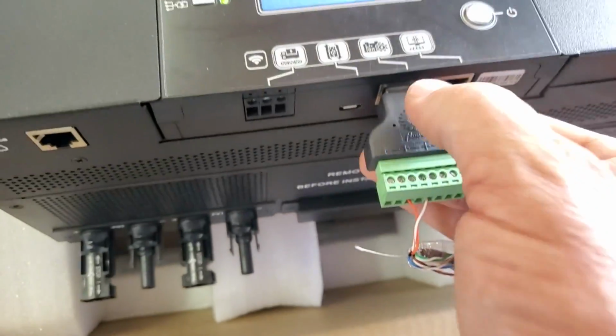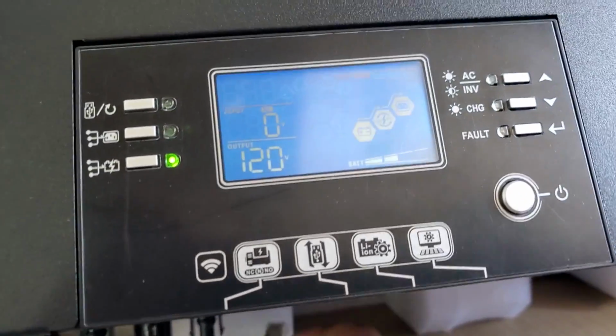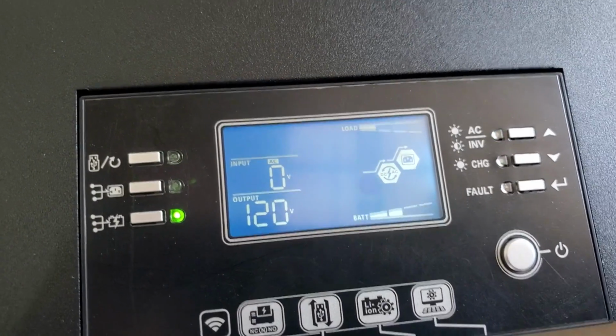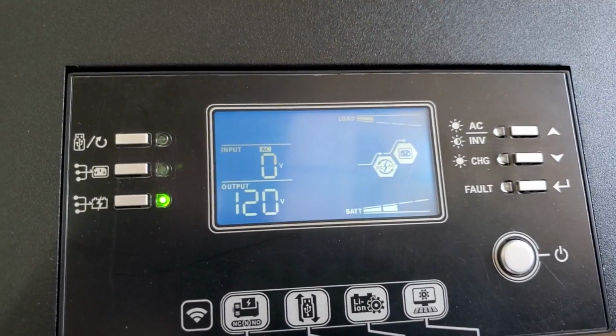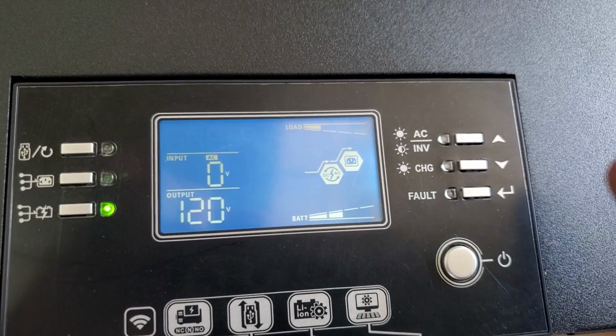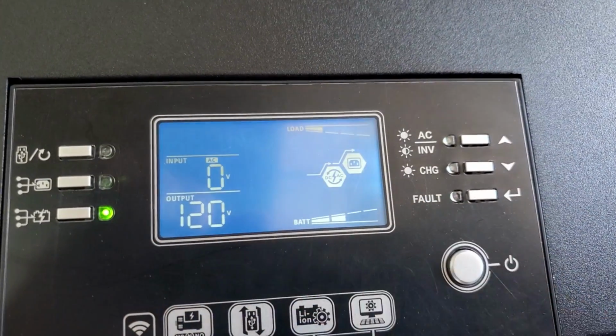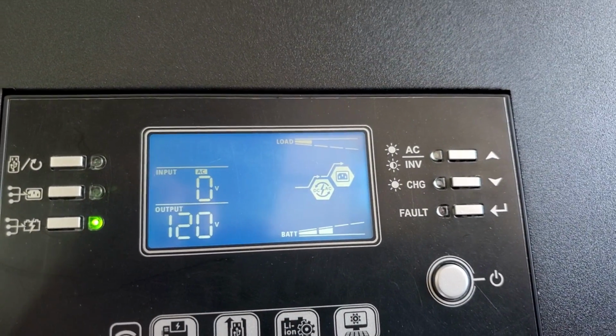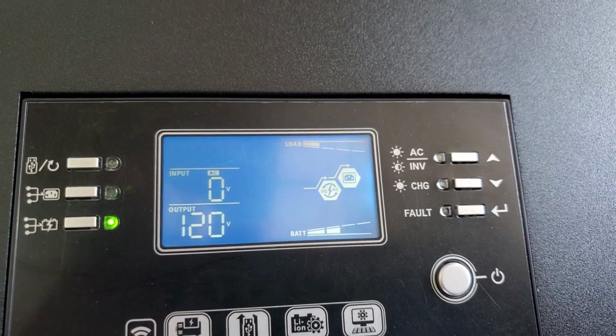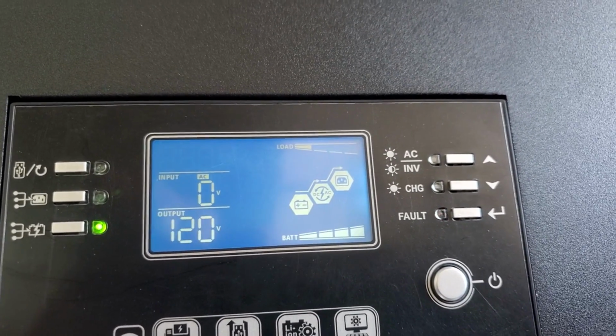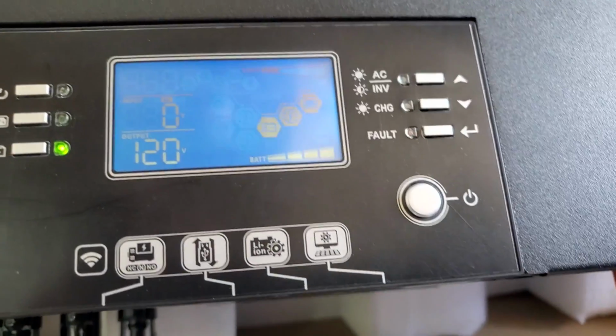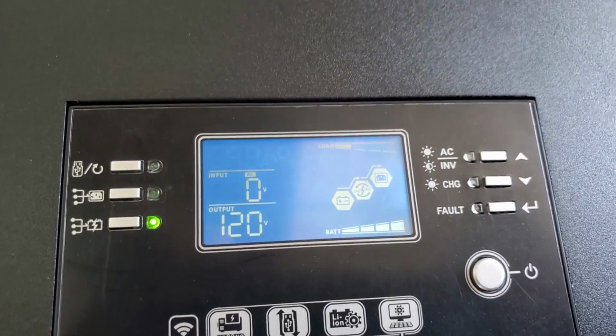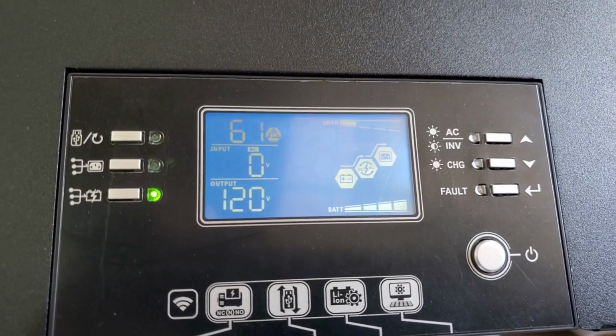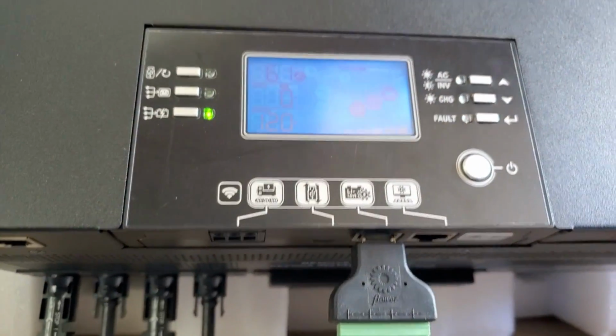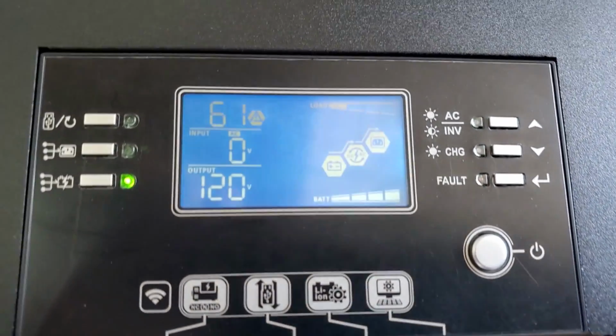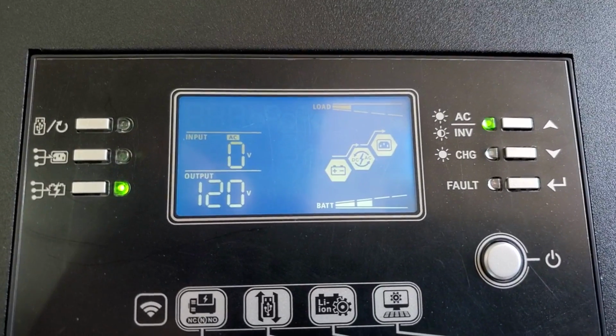There you go, the battery is now communicating with the inverter. If we pull this plug out, you'll notice we're not trying to pull the wool over your eyes. Within a short while we'll get a fault light, fault 61, and the inverter will shut down after 12 minutes. So there you go, fault 61 — just to prove no firmware update is needed. We put the cable back in, and a few seconds later fault 61 is gone.